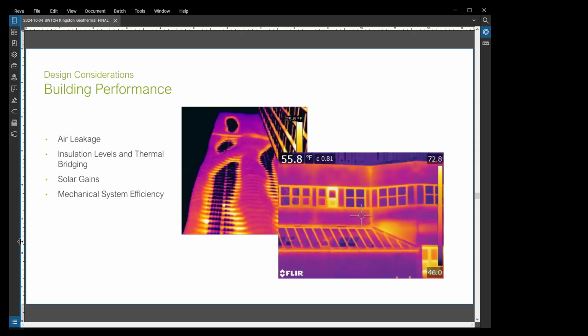Building performance is really the big ticket item now. How does your building perform aside from the geothermal system? That has a huge impact on what your geothermal system needs to be. If you're taking care of air leakage and not losing the preconditioned air we talked about, you're putting less work on your geothermal field, so you can make it smaller. If you have well-insulated walls and aren't just spitting conditioned air out, again you put less effort on the geothermal system, so you can make it smaller. Solar gains too - are you employing passive shading, or making sure your glazing ratio isn't out to lunch, so people aren't overheating when they don't need to be? That reduces your cooling demand, so you can potentially make the field smaller. And then the overall efficiency of the mechanical system - if it's more efficient, with every turn of that loop you require less and less, which can also reduce the size.